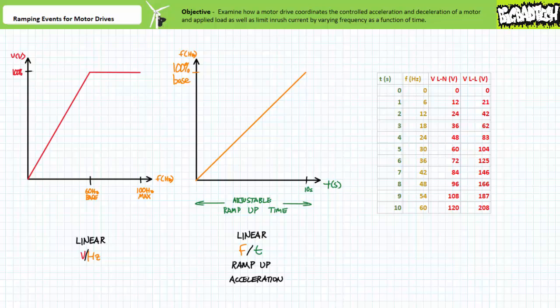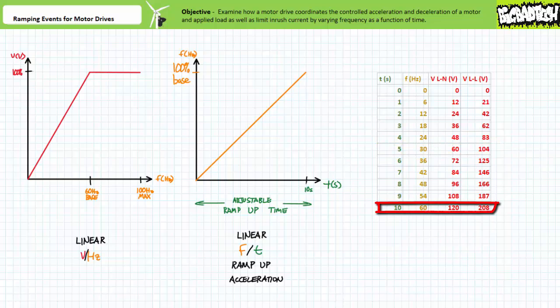Consider a motor drive with a simple linear volts per hertz profile and another plot of frequency as a function of time, where excitation frequency is ramped from zero to the base frequency over an adjustable acceleration ramp-up time of, let's say, 10 seconds. Assuming a 60 hertz base frequency, this means while excitation frequency is ramped from zero to 60 hertz over 10 seconds, voltage is also ramped from zero to 100% over the same 10-second period. At five seconds into the ramp-up event, excitation frequency would be 30 hertz and applied voltage would be 50%. When the ramp-up event finishes at 10 seconds, excitation frequency flatlines at 60 hertz, as does applied voltage at 100%.